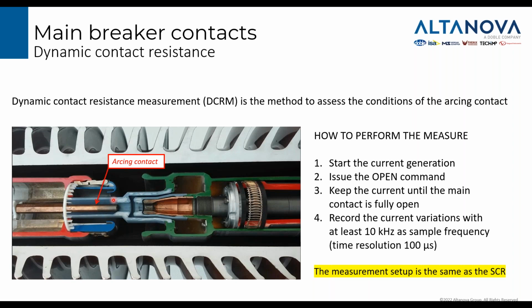Arcing contact must be in good health. So what you need to check the status of the arcing contact is to, for example, start the current generation. When I mean current, I mean the DC current generation. Then you issue the open command. You keep the current until the main contact is fully open, and you have to record the current variation with at least 10 kilohertz. That means a time resolution of 100 microseconds, because the operation is very fast.